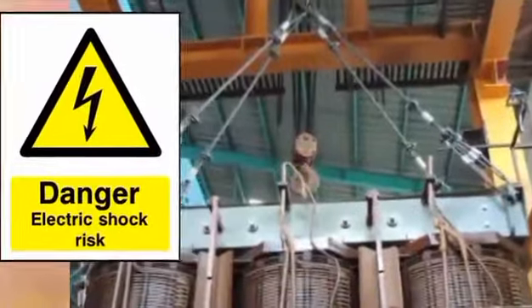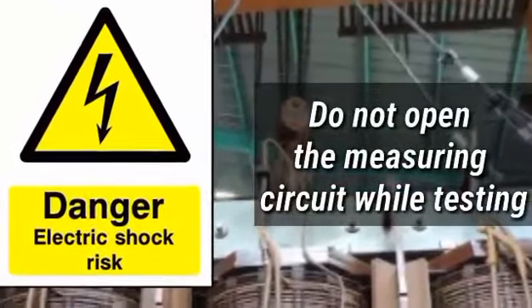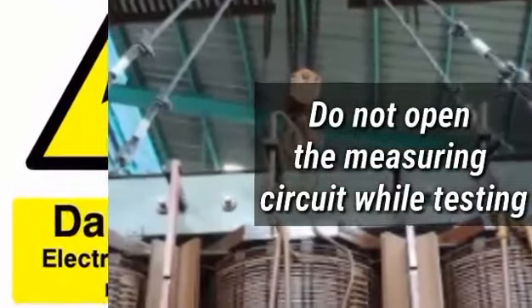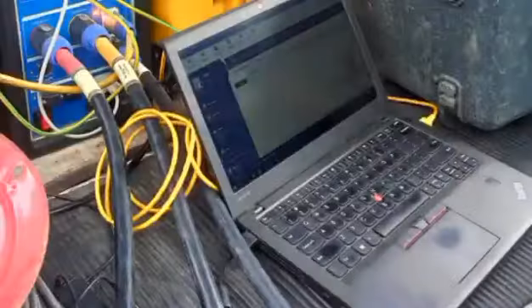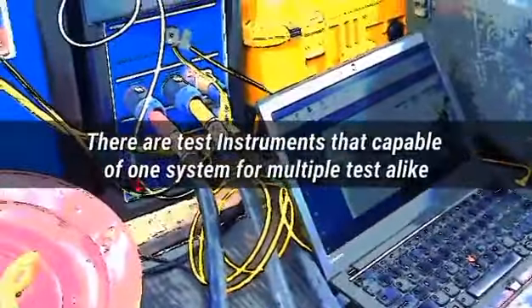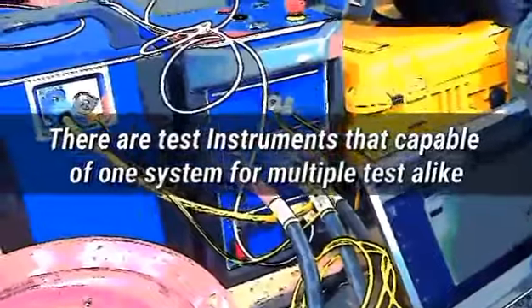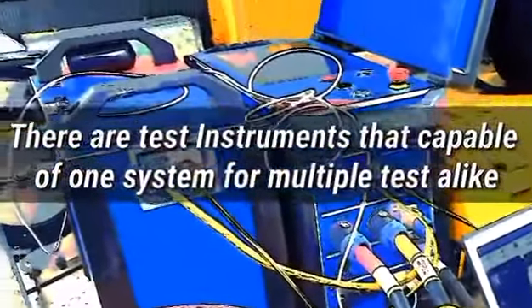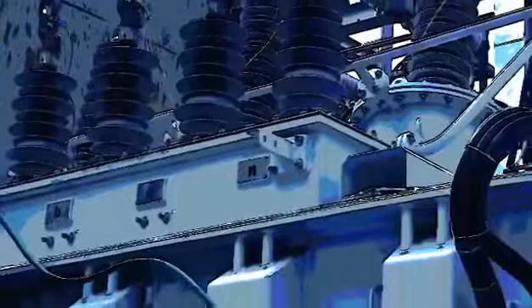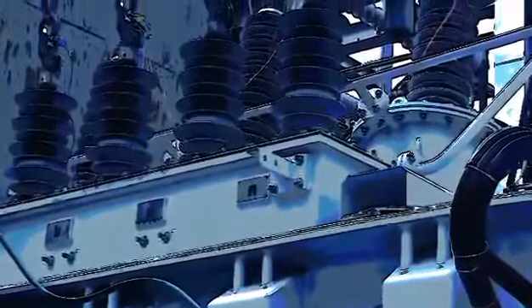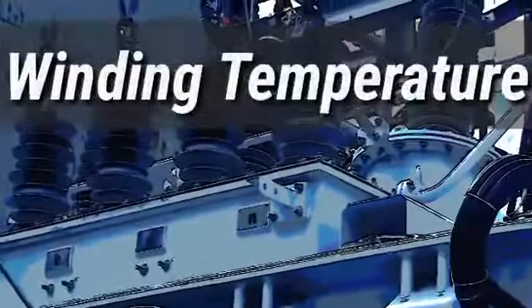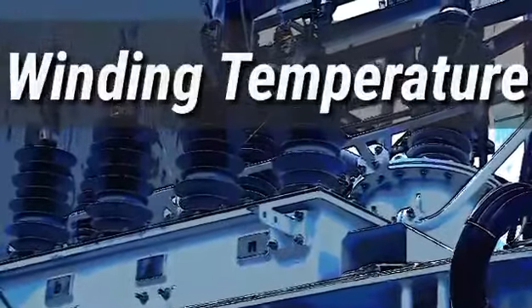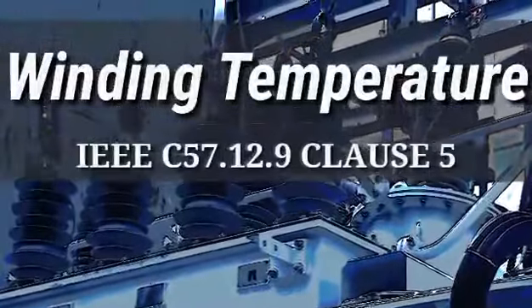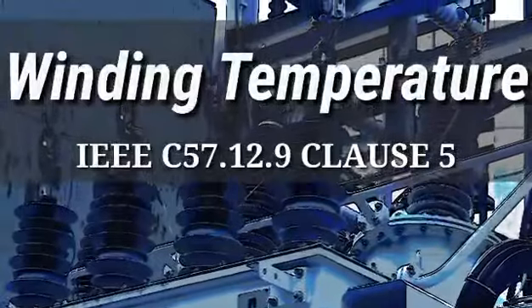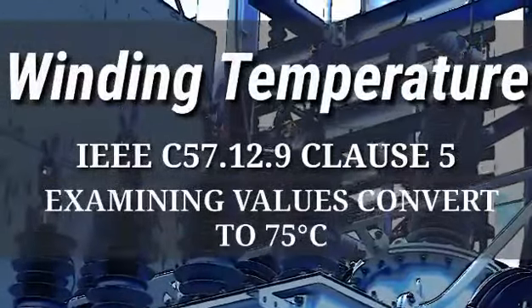Please be mindful that in analogous tests you must never open the measuring circuit while the current flows. Dangerous voltage may occur. Nevertheless, there are test instruments that are capable of one system for multiple tests alike. Just 3 cables need to be connected to perform various tests, especially the DC winding resistance test. Another important item to take into consideration is the winding temperature at the end of a temperature test, which is very useful to coincide with the reference standard IEEE C57.12.90 Clause 5 that we are using.